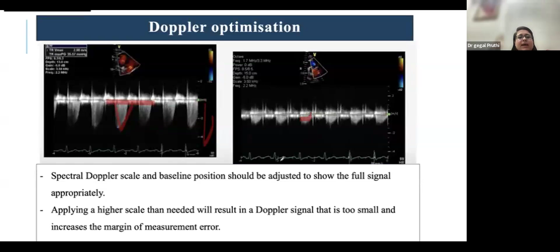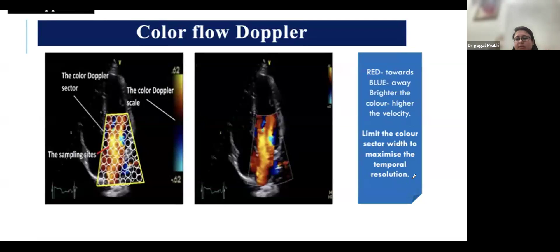In color flow Doppler, since it is also a type of pulsed wave, there is a limitation of low temporal resolution. So the color sector should be as small as possible, adjusted to include the region of interest. You have to limit the color sector width to maximize the temporal resolution.